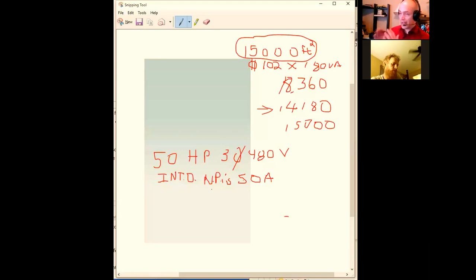So you've got to draw a line either in the sand on that page or in your mind if you're dealing with a branch circuit wire. And this is the only place it matters. If you put that sucker in as the biggest motor in a group of motors, the size of feeder for it, then it's a continuous duty motor. And what you just did would be correct as the first step. But when it's just the branch circuit wire where you've got nothing else, you just take the nameplate rating. The nameplate value. So 50 times 85% then comes out to be.